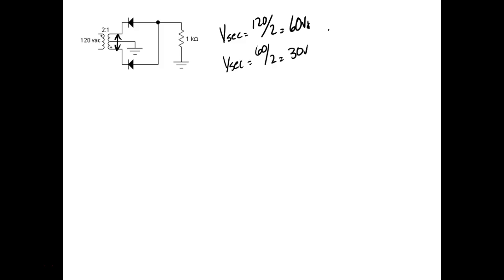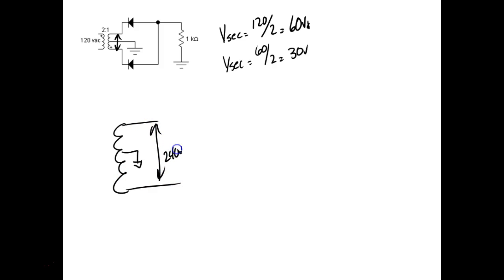When we give the voltage across a center-tap transformer, we give it all the way across. So if you were at home and they said what do we have on that power pole — you've got a 240-volt center-tap transformer. It's center-tap, so if I come over here and I say I have a 240-volt center-tap transformer, that's 240 volts all the way across. But I'm only using half of the transformer, so that's 120 volts — and that's the way your house is wired.